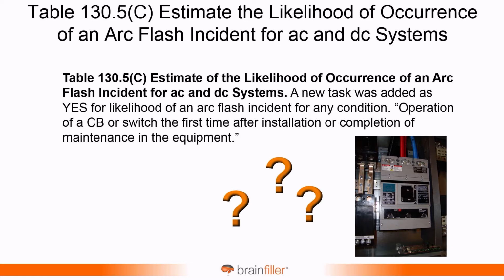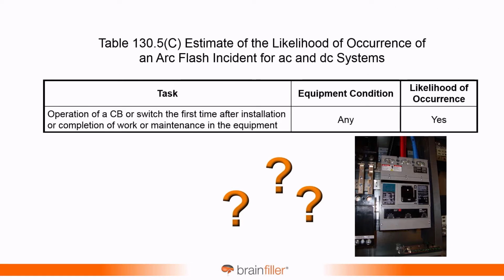No. You know, is there a huge likelihood when you energize a breaker? Well, I can't contradict this, but within NFPA 70E, the rationale is yes, the first time you're operating a circuit breaker or a switch, after its installation or after completion of work or maintenance. Over on the far right, likelihood of occurrence of an arc flash? Yes, that is a new change to the 2021 edition of NFPA 70E.